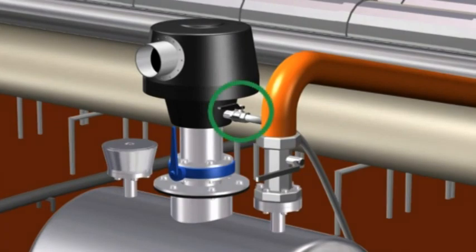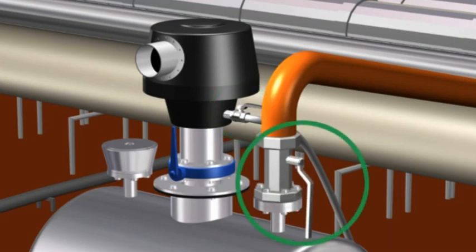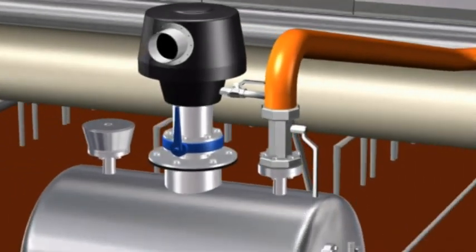The ejector is driven by compressed air and consists of no moving parts, which means that almost no service is needed. Nitrogen can also be used if the compressed air line cannot deliver enough volume. Then the valve for the suction inlet on the AB950EX is to be opened.